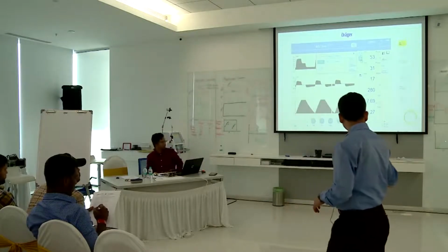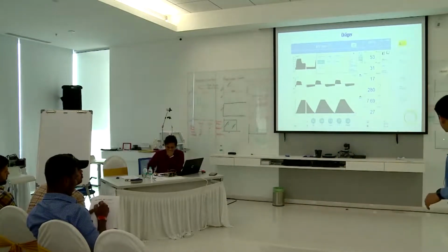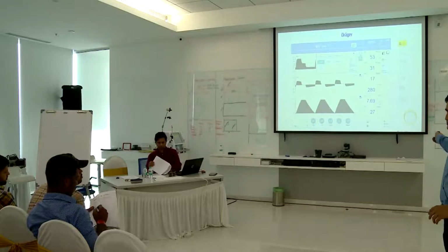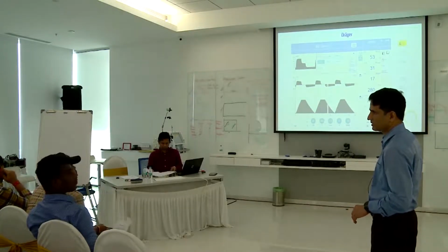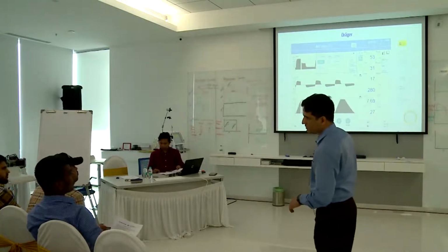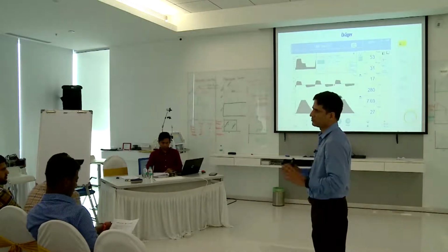Like this, see, the volume time graph is not reaching your baseline here. Ideally it should come like this, but here it is not coming to the baseline. So there is a leak in the circuit. So always remember this. Whenever you see your volume time graph is not reaching the baseline and there is a difference between your expired tidal volume and the inspired tidal volume, that means there is a leak in the circuit. So this is the basis of your ventilator graphics.